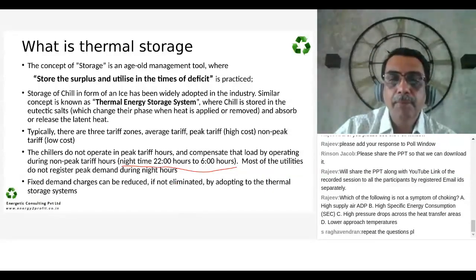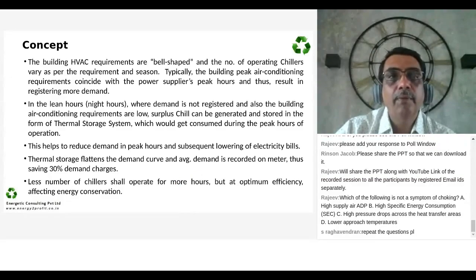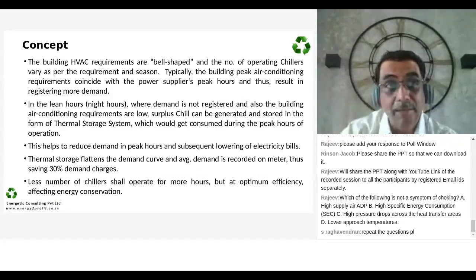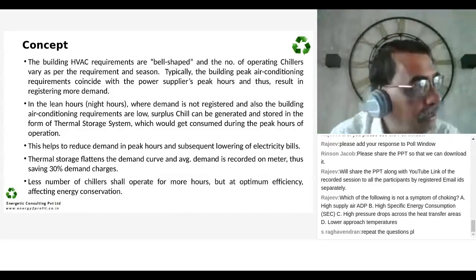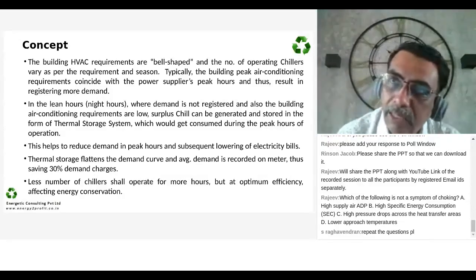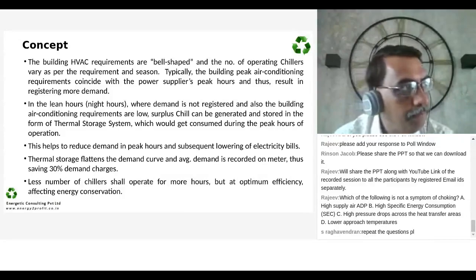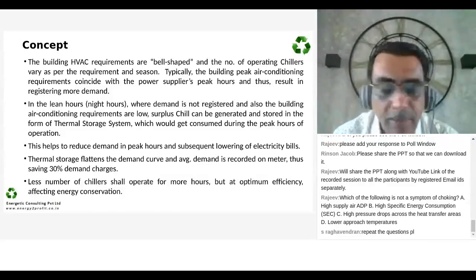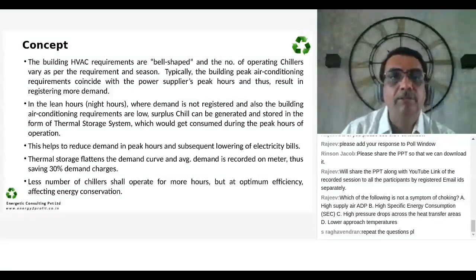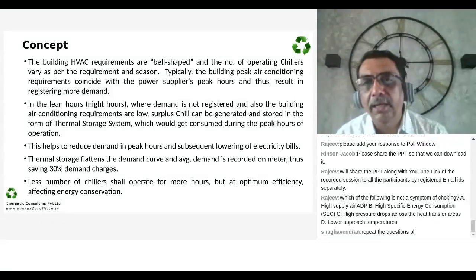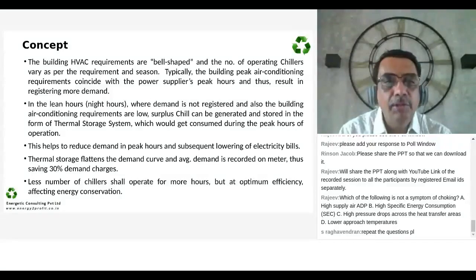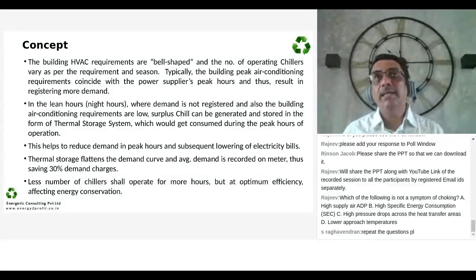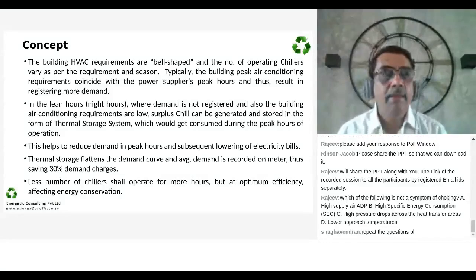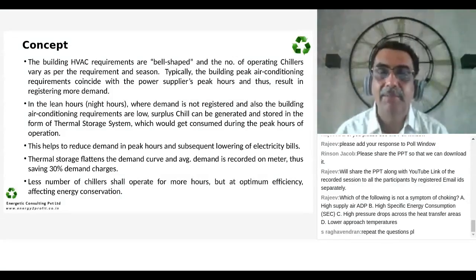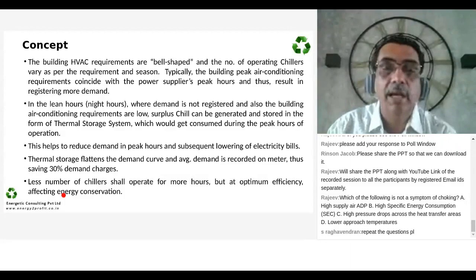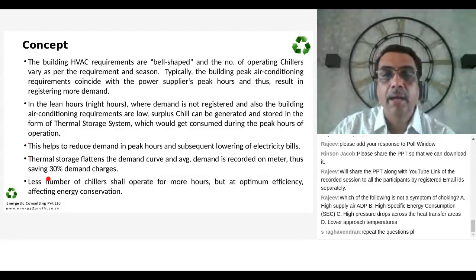Now, what am I trying to do? The concept says that the demand curve is bell-shaped, which means that it is low during the morning hours and low during the night hours, and during the day hours it is at peak. So I'm slashing the top portion of the peak and pushing it into the lean session, which means that we are not operating the system when the demand is maximum and the energy charges are maximum, and therefore we are reducing our maximum demand by around 30%.